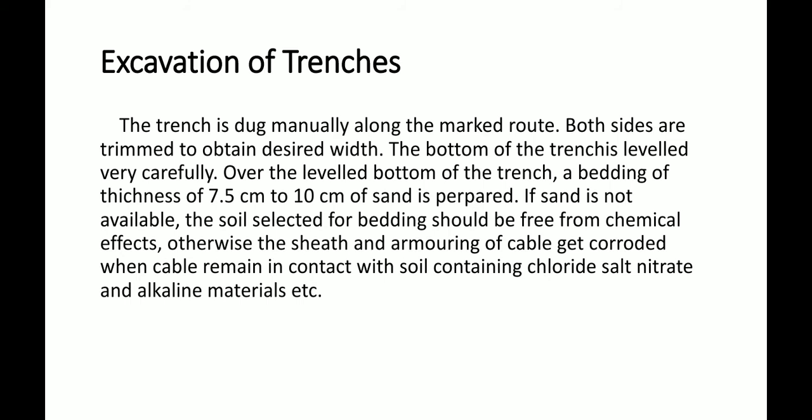The bottom of the trench is levelled very carefully. Over the levelled bottom, a bed of thickness 7.5 cm to 10 cm of sand is prepared. If sand is not available, soil selected for bedding is used. The soil should be free from chemical effects; otherwise the sheath and armoring of the cable get corroded.